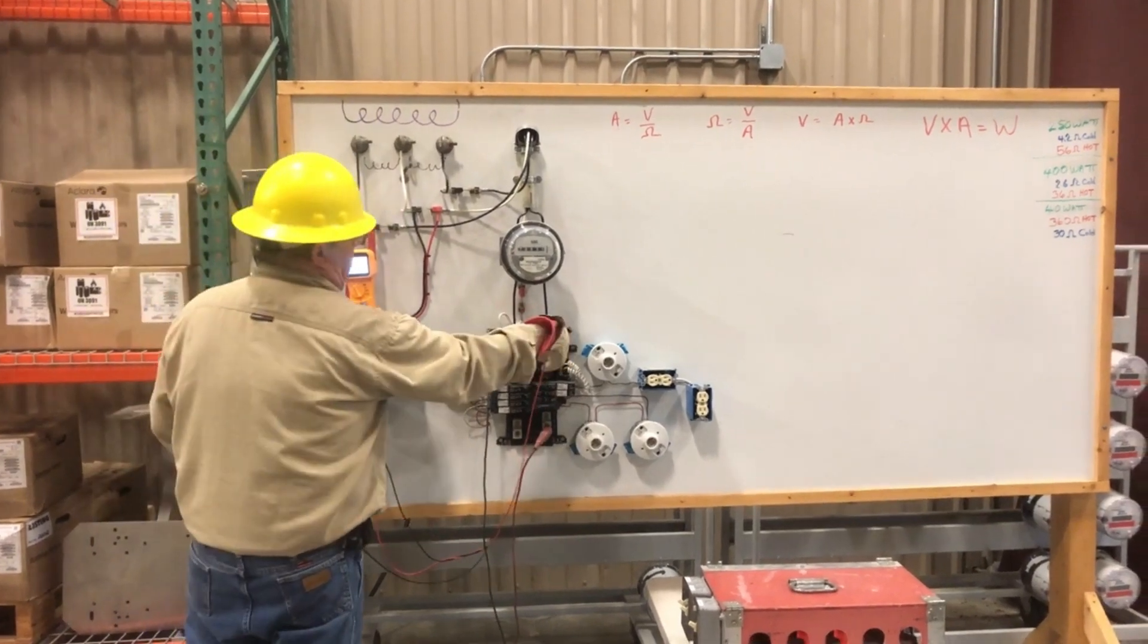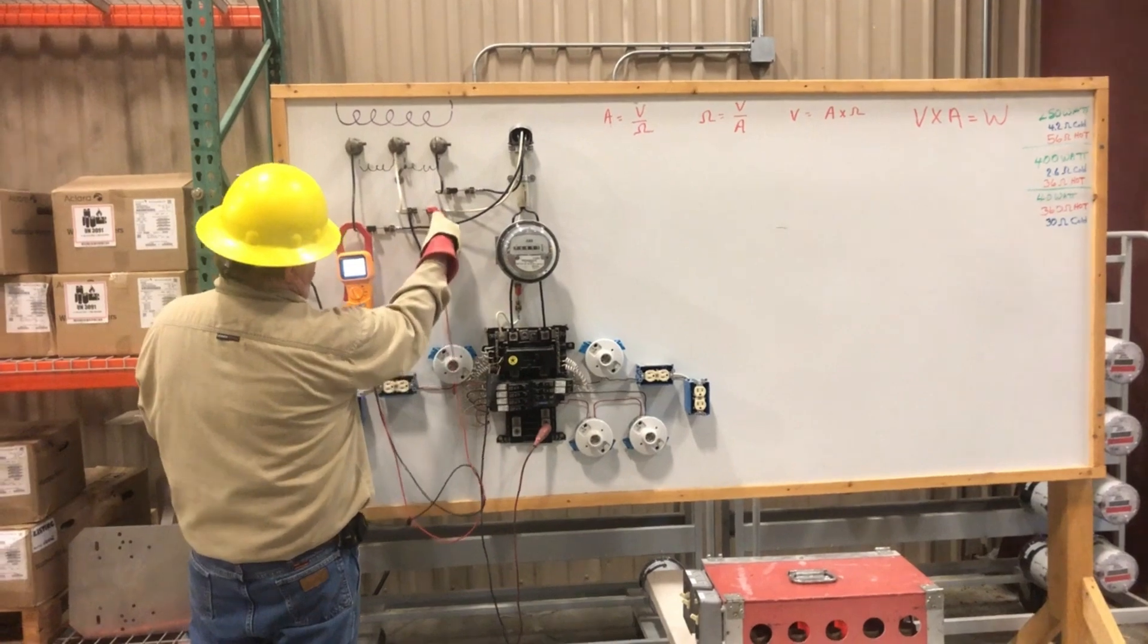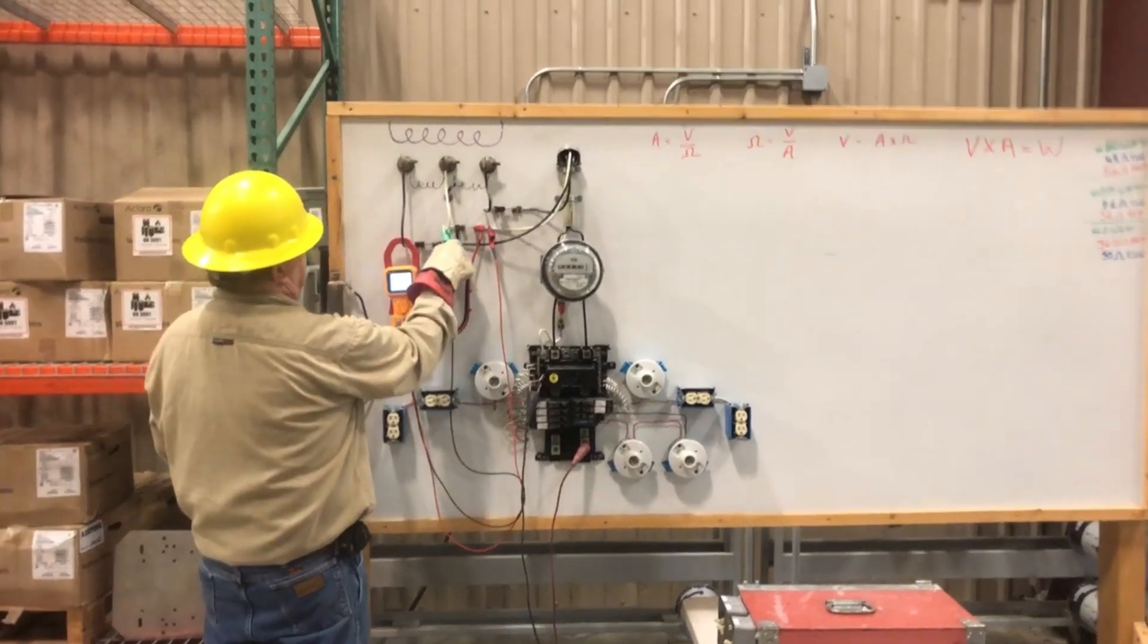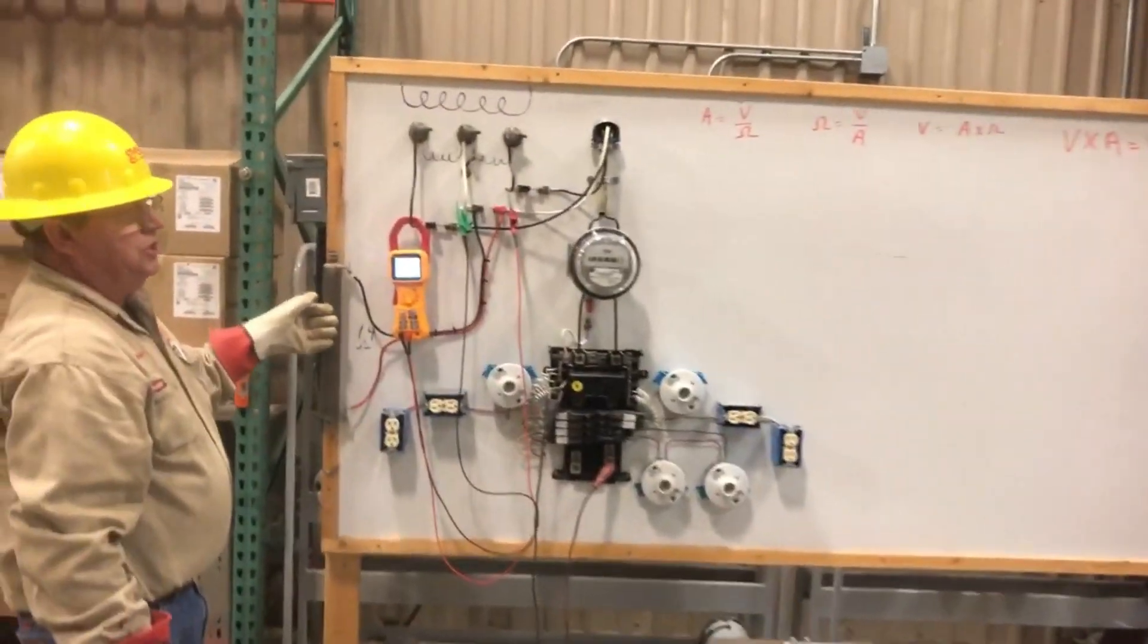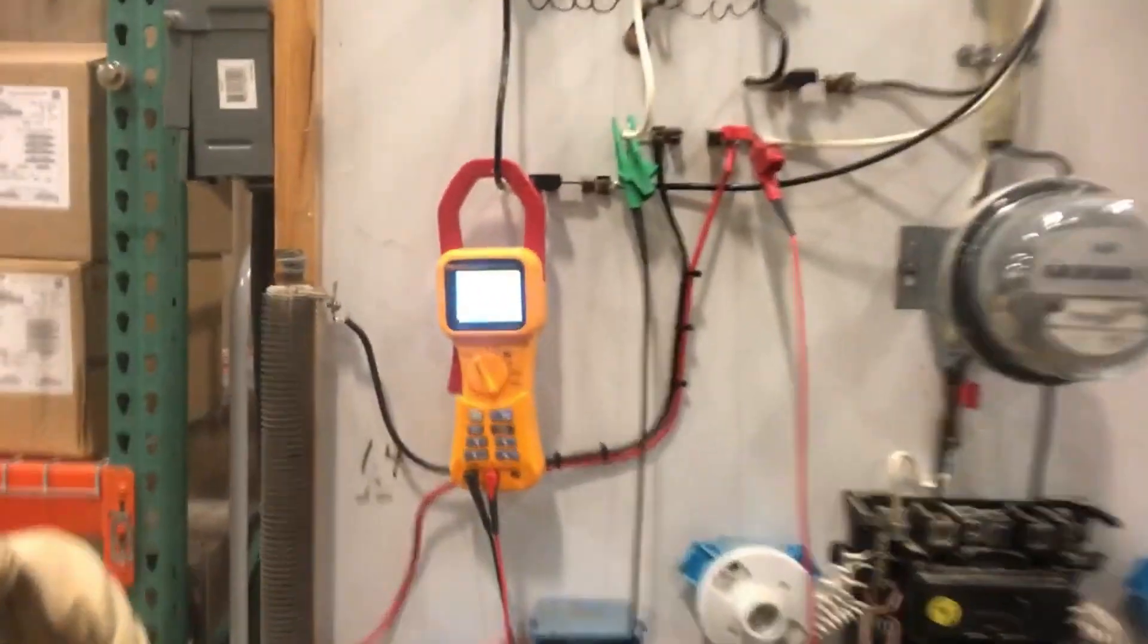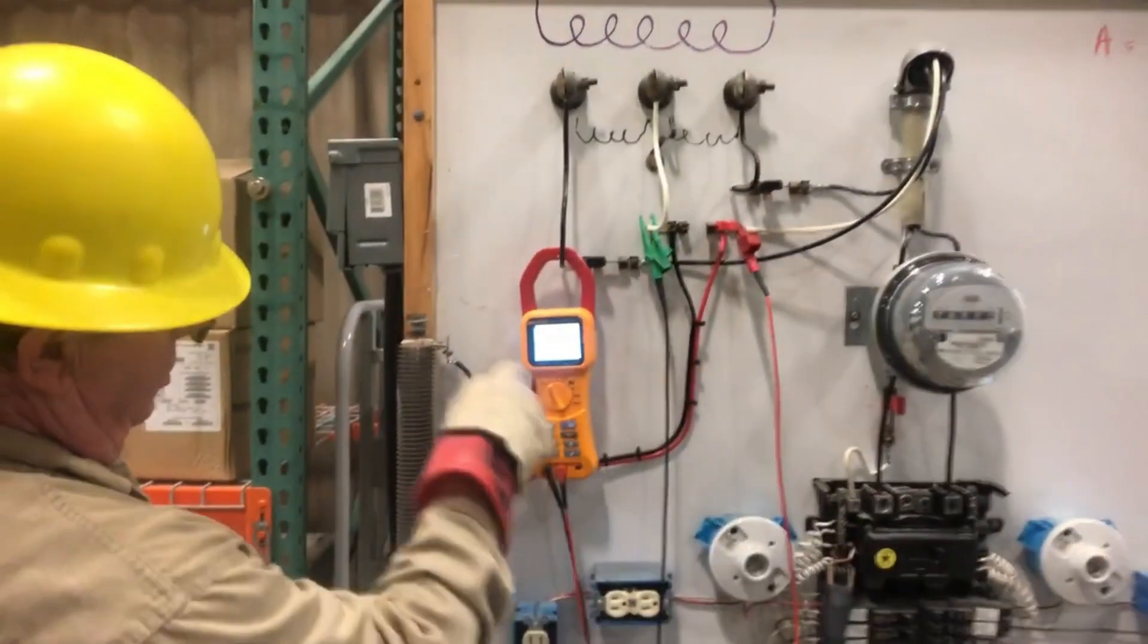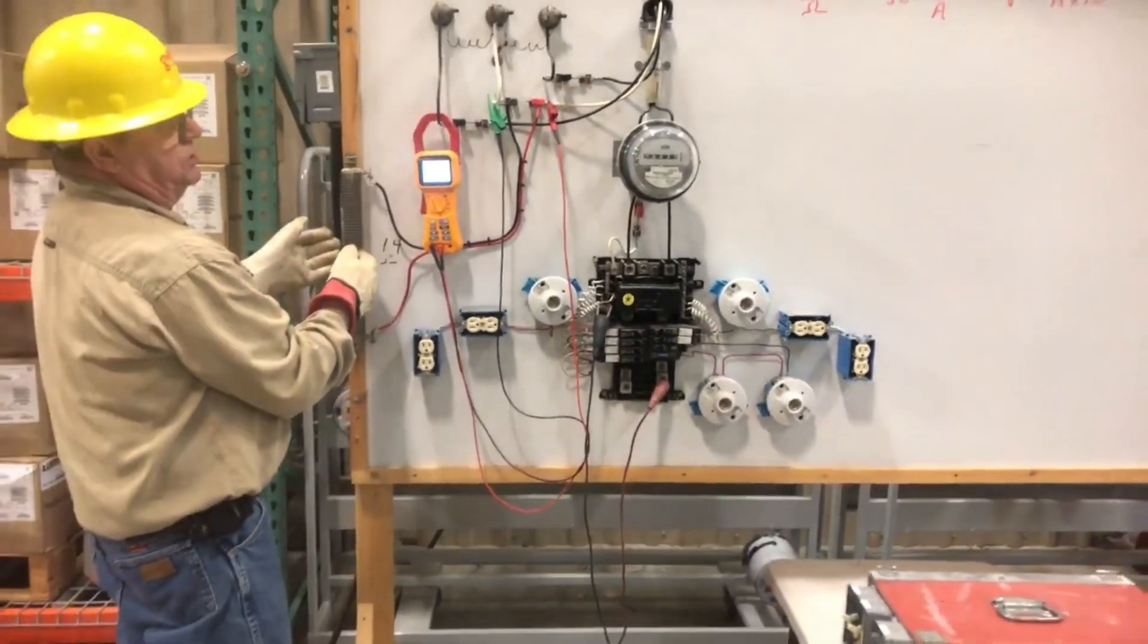We come and we take this voltmeter lead, two voltmeter leads. One is on the north side of the bad resistor or the bad connector and one is on the other side. This resistor has cost 25 volts worth of voltage drop. 25 volts is what it costs across this connector. If you watch the route, you can see the only thing that's on that wire is this resistor.